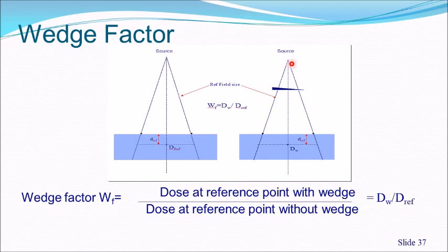When a physical wedge is used in the radiation beam, it attenuates the radiation reaching the patient. To account for this, a wedge factor is applied: wedge factor = dose at reference point with wedge / dose at reference point without wedge. Linac or cobalt units typically come with four wedge angles: 15°, 30°, 45°, and 60°, and the wedge factor must be determined for each.